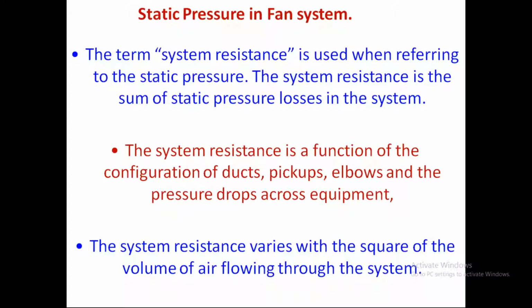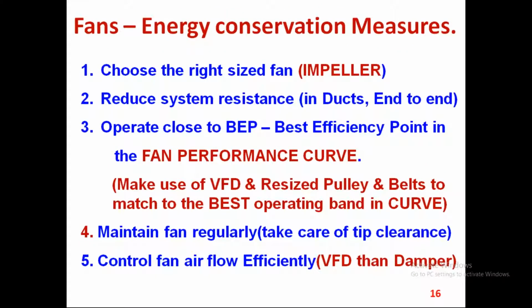The system resistance varies with the square of the volume of airflow across the system. This is as per the fan's affinity laws. We are trying to attach the fan affinity laws not only for the kilowatt, it is for the static Pascal, it is for the flow rate, and it is for the speed, the RPM, that is the flow. So for the existing centrifugal type fan, what energy conservation measures can be done?